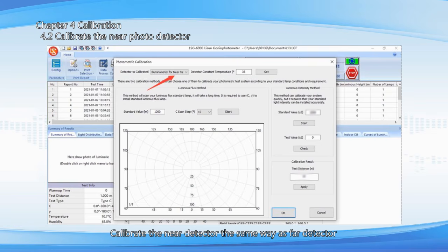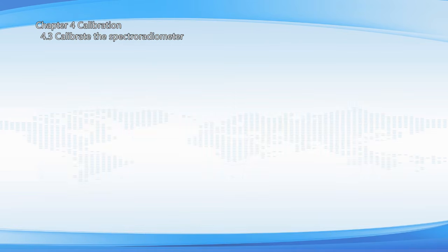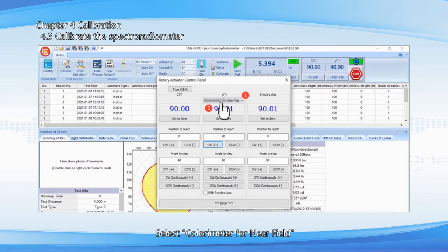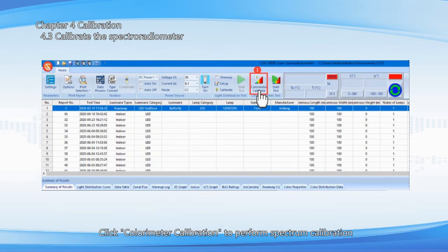Calibrate the near detector the same way as the far detector. Calibrate the spectroradiometer. Select colorimeter for near field. Rotate the gamma angle to the 90-degree position. Then the light of the standard lamp will go through the hole of the lamp holder and go to the optical fiber directly. Click colorimeter calibration to perform spectrum calibration.